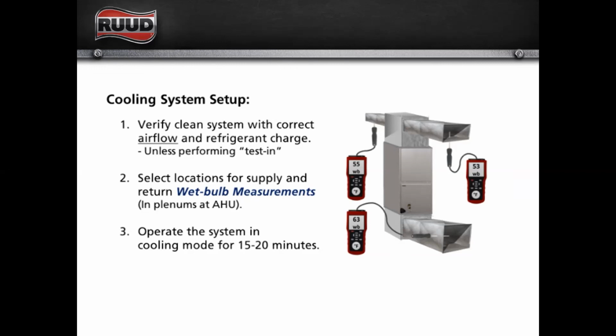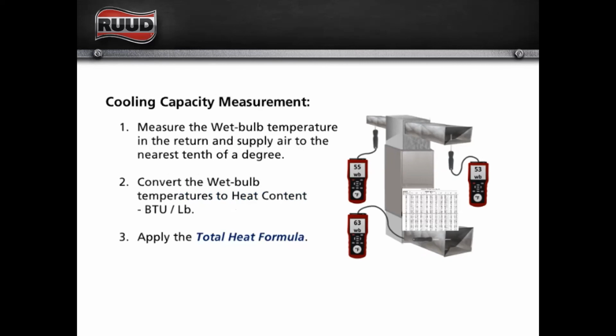Once you start dehumidifying and you see water coming out of the drain, then you can measure wet bulb temperature. And we're checking wet bulb. We've got a single return, and then we've got two supply runs. So we're going to check on each one of those supply runs and our return. So we got a 55 on one of our extended plenums on our supply. We got a 53 on the other one. We're just going to average those together, right? Which would be 54 wet bulb. And then our return wet bulb is 63 degrees.